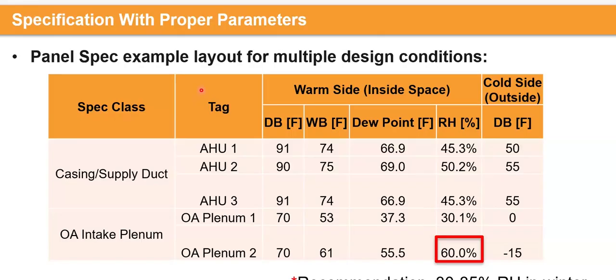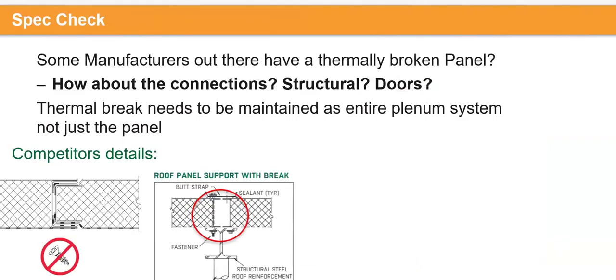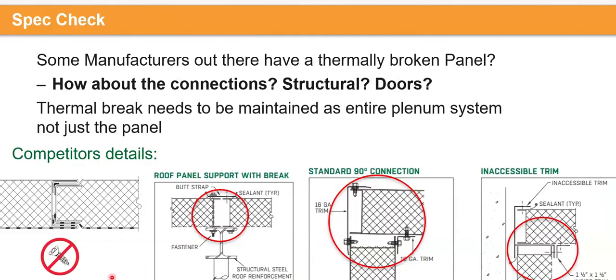I want to just hop in real quick. The reason that SEDEM is putting this information out there is because, as a rep, and I'm sure SEDEM and Mauricio and Jackson see panel specs all the time, I've never actually seen one that had a performance that was based on the entire assembly. So when you're asking for a 4-inch panel and your assumption is, well, this is an outside air plenum, I'm fine. The truth of the matter is nobody really has done a decent job of articulating this, whether that's any of the competitors that build or a contractor that builds double wall panels, which is not that hard to do. We need to be more clear about what the panel itself does, but more importantly, what the entire assembly does. Because when you put a bunch of bolts through it, it's not what you thought it was when you specified it in the beginning.